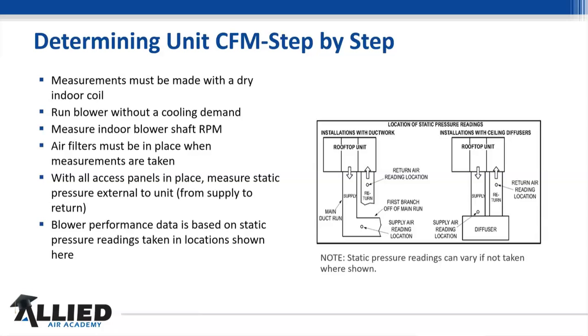So we're going to determine the CFM, and there's a lot of different ways to do this, and I'm going to show you the RPM way. And I do realize that in some states you can't operate a unit with the blower door off. I understand that, and we'll have to have different methods to do it. This is one of the easiest methods to do, and it's one of the more accurate methods as well. So, measurements must be made with a dry indoor coil.